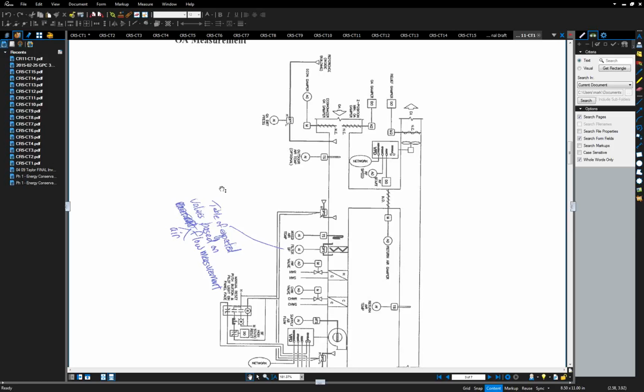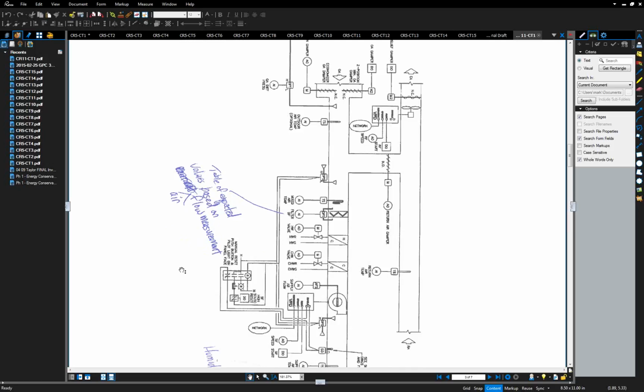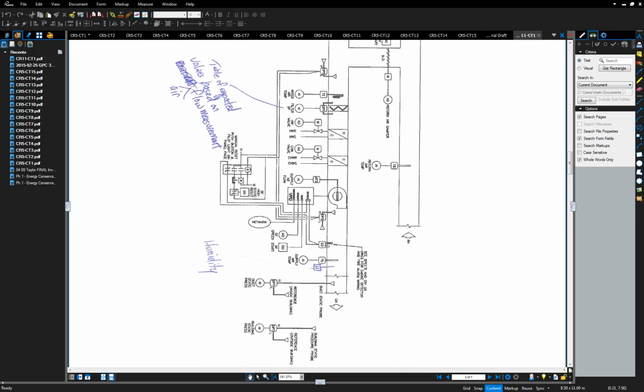I don't know if I can actually turn the screen on this, but it says a table of expected values based on airflow measurement. Yeah, this was for variable. We found that when you have a DP sensor across a filter for an alarm, that expected pressure obviously changes as you ramp up or speed up or slow down the fan.